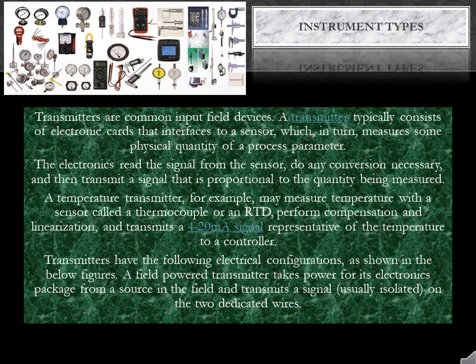Transmitters are common input field devices. A transmitter typically consists of electronic cards that interface with a sensor, which measures some physical quantity of a process parameter. The electronics read the signal from the sensor, perform any necessary conversion, and then transmit a signal proportional to the quantity being measured. For example, a temperature transmitter may measure temperature with a thermocouple or RTD, perform compensation and linearization, and transmit a 4–20 mA signal representative of the temperature to a controller.